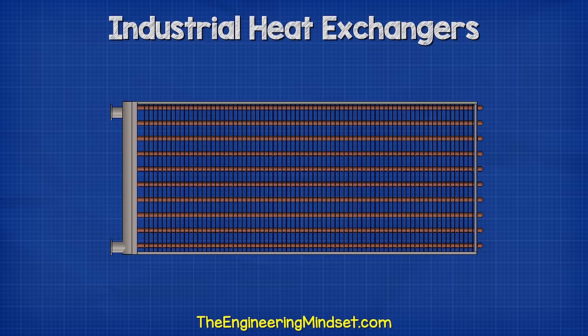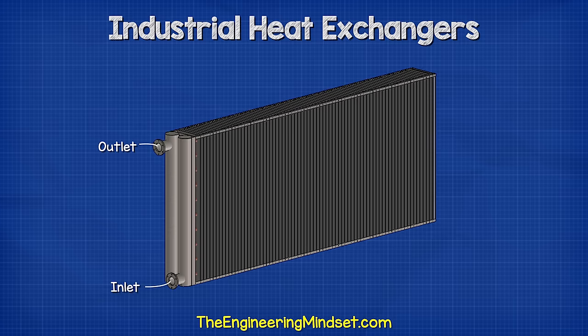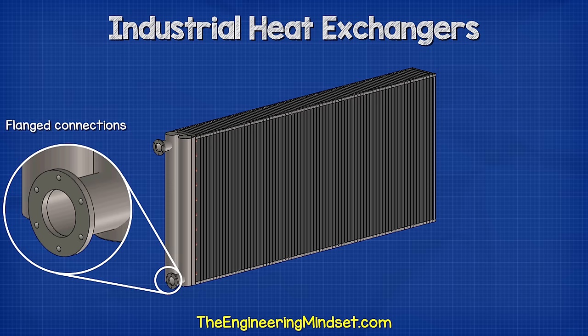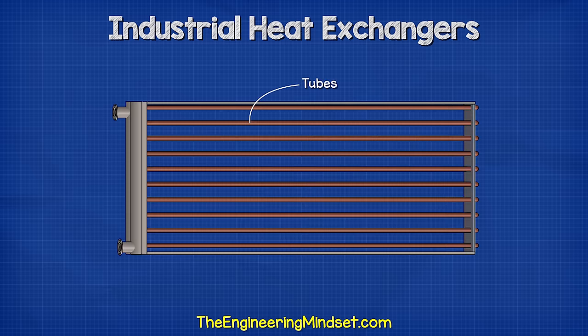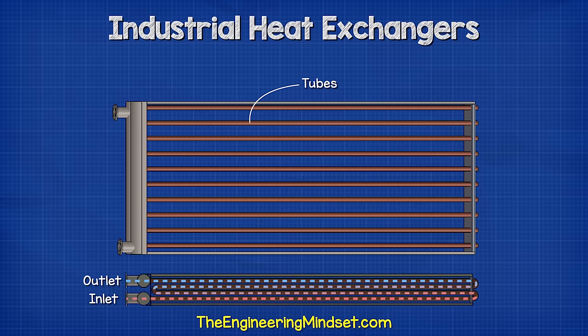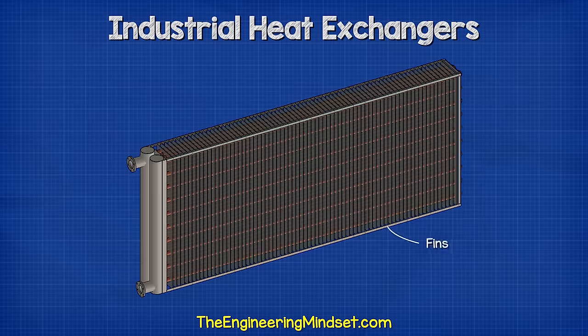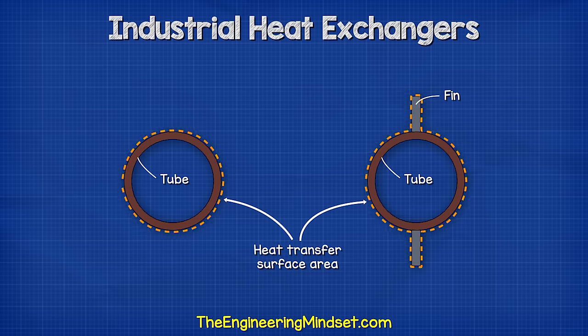A typical fin tube heat exchanger has an inlet and an outlet, both usually located on the same end. These connections are typically flanged, but they could be threaded or soldered depending on the application and working fluid pressures. Running between the inlet and outlet is a tube which contains and directs one of the working fluids — for example, hot water. The tubes are covered with many thin sheets of metal known as fins, which increase the surface area of the tube wall, allowing more heat to transfer.